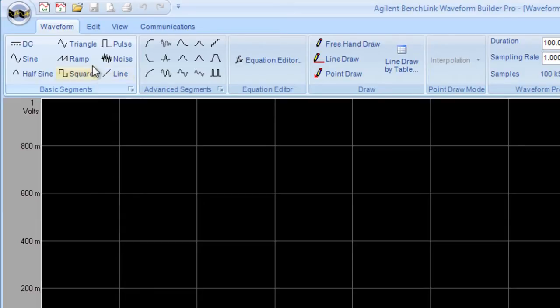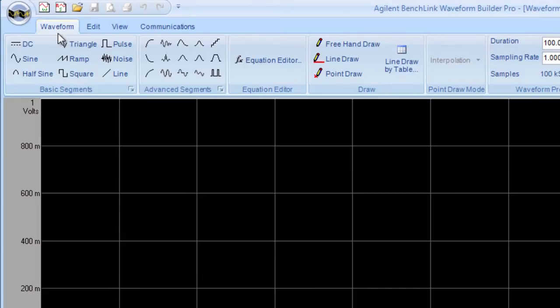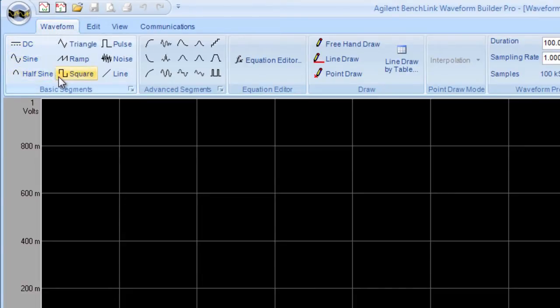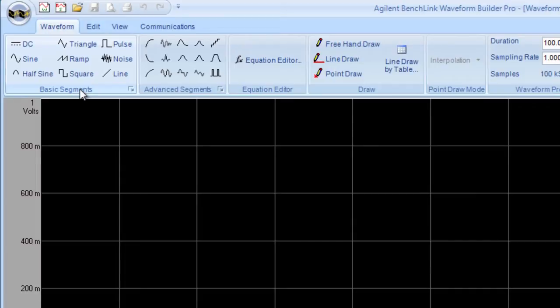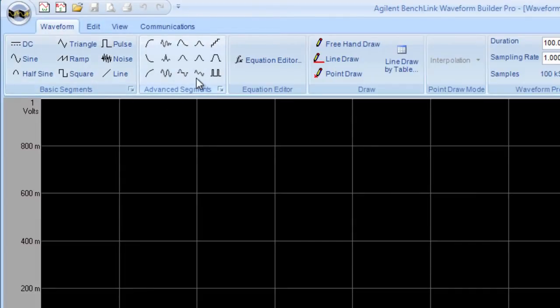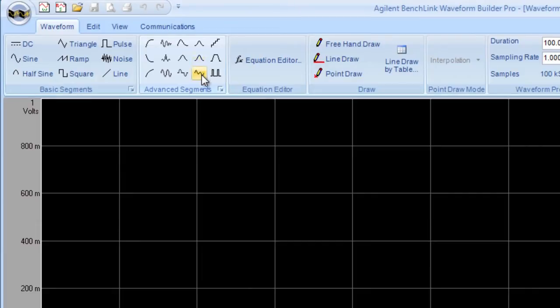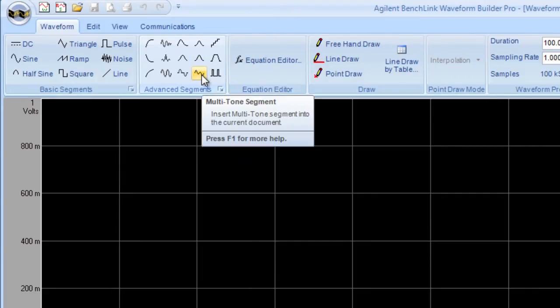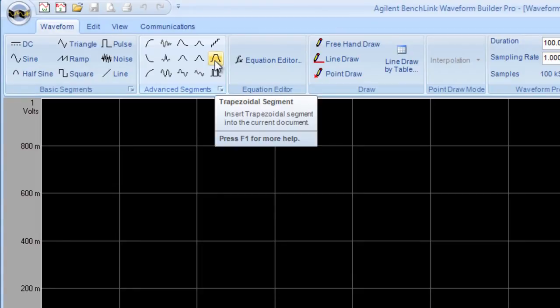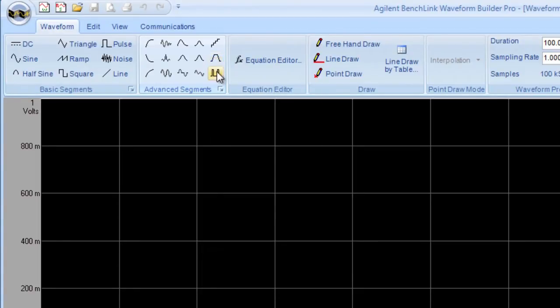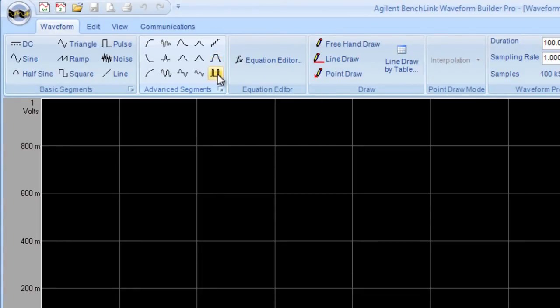So first under the waveform menu is basically where I do the creation of the waveform. I have one section here that are basic waveform segments, much like the ones that are built into the function generator. I have some advanced segments that get a little more complicated, things like a multi-tone segment, a trapezoidal segment. And in fact you can even build a serial data segment.